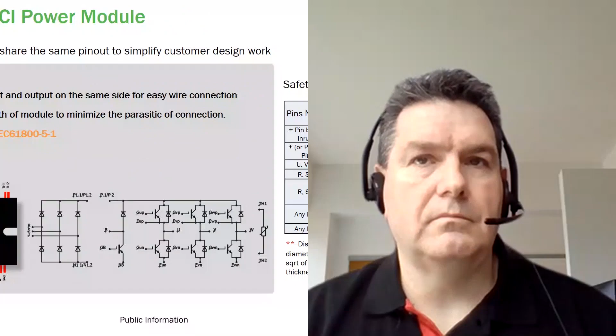You can see on the table here that we have more spacing than needed, and in those calculations, shown in the green column, we've accounted for the pad dimension with some drilling tolerance and so on. So this is really a minimum you will have between pins, and you don't have to worry about safety—you just place the module, make the layout, and you respect all the safety distance needed.